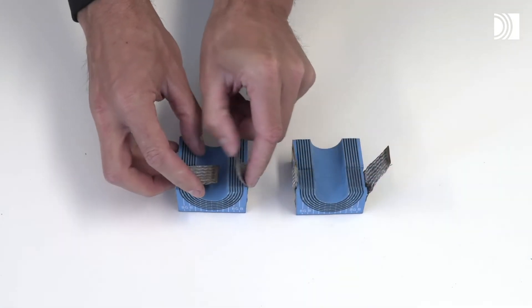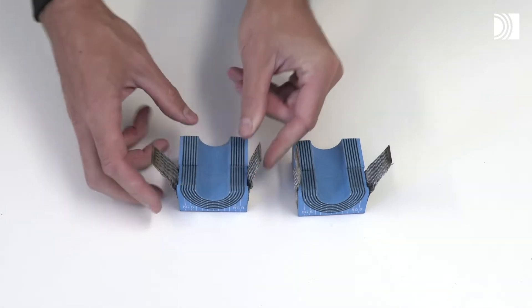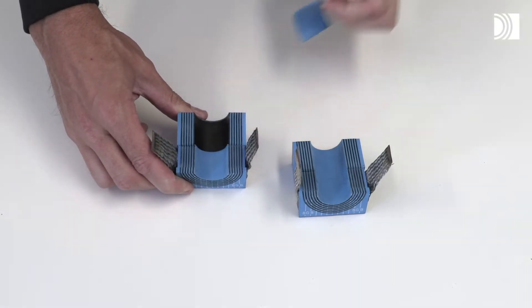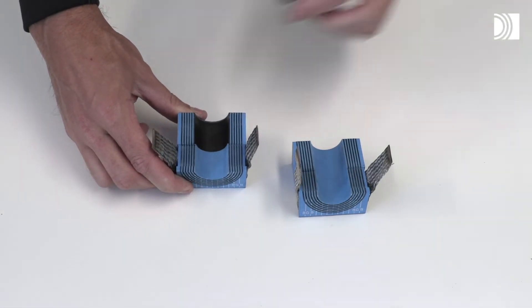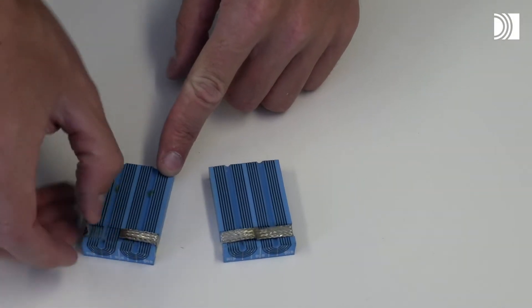Adapt the module to the cable jacket by peeling off layers from the environmental protection side and to the cable armor by removing layers from the termination side. The number of layers must not differ by more than one between the module halves.